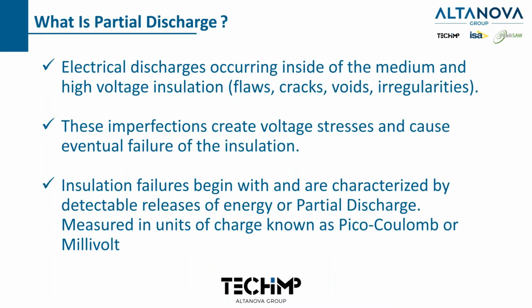All right, so let's start with what is partial discharge. I think a lot of you already know what partial discharge is, but let's just review it real quick. Basic understanding of partial discharge is nothing more than a spark or an arc that happens inside the insulation of an asset, whether it's cable would be internal or tracking or corona discharge.